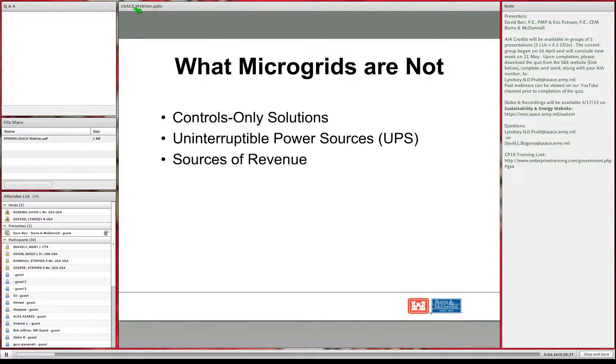People also confuse microgrids with uninterruptible power. They're really not the same. You can have a UPS as a component of a microgrid, but the microgrid itself is not a source of UPS power—it's just a way of using different generation assets with different loads as necessary. There really isn't a payback for a microgrid itself. Assets within it can have payback, but the microgrid configuration doesn't provide a payback on its own.